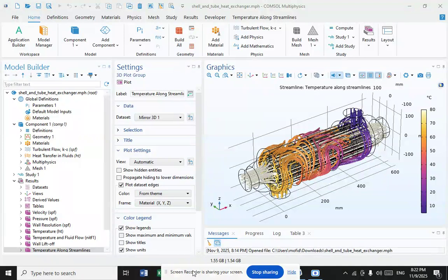Double pipe heat exchangers are the simplest exchangers used in industries. On one hand, these heat exchangers are cheap for both design and maintenance, making them a good choice for small industries. On the other hand, their low efficiency coupled with the high space occupied in large scales has led modern industries to use more efficient heat exchangers like shell and tube or plate.